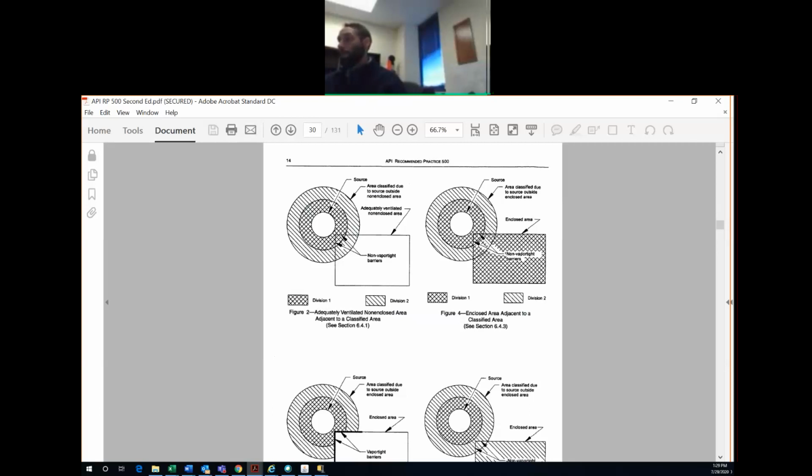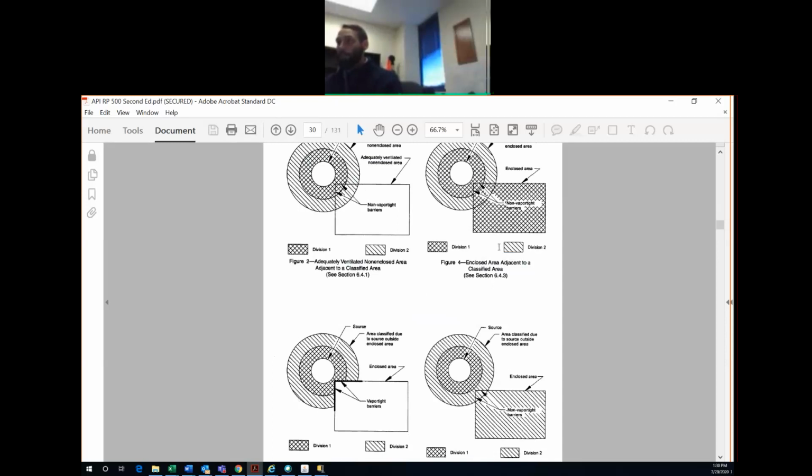Well, now the whole enclosure is Class 1 Div 1. And that's tough because now you have to put all the electrical equipment in there. It's got to be in NEMA 7 enclosures, and it's extremely expensive and heavy. And it's going to be tough to specify all of the electrical equipment in that building to be rated for the area. So that's not a good situation.